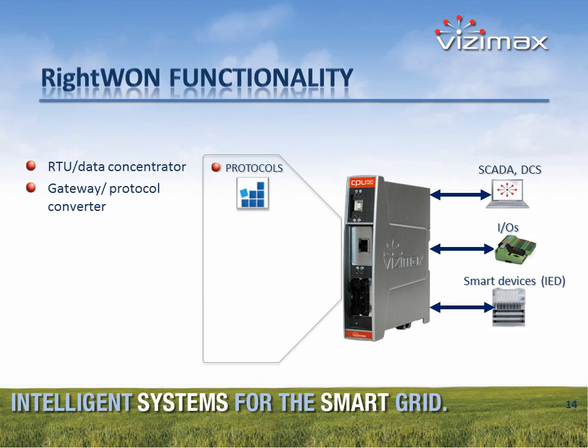First of all, the RightWON supports many communication protocols, including Modbus, DNP3, IEC 61850, GOOSE, IEC 60870, OPC DA, and many other communication protocols, either as master, slave, or as client, server on both Ethernet or serial communication links. Therefore, the RightWON can be used as an RTU, a data concentrator, a gateway, or a communication protocol converter, enabling incompatible devices to talk together.